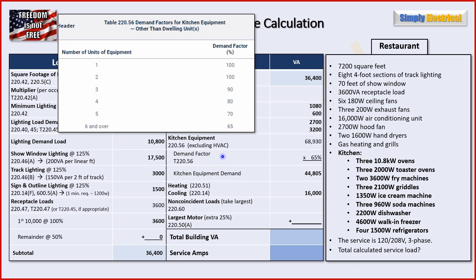For kitchen equipment, we go to 220.56, which tells us to count the number of units and take the corresponding demand factor. We have 21 pieces of kitchen equipment. The table goes down to five units, and six or more gets a 65% demand factor. We total all the kitchen loads together — that comes to 68,930 watts. Multiplying by the 65% demand factor gives us 44,805 VA.